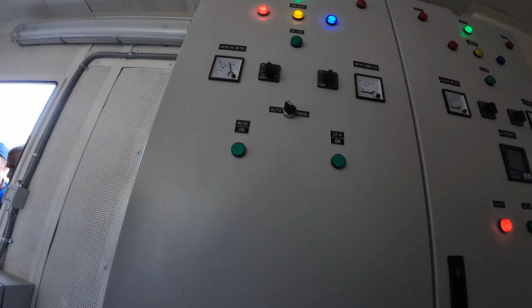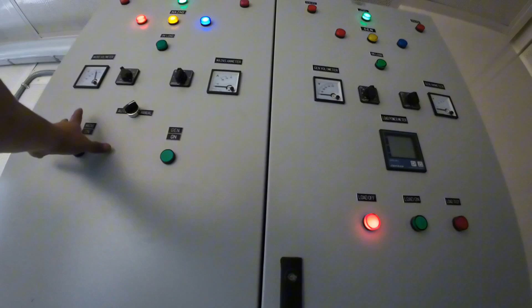Okay, so we will try to run this generator, so at least we have it available for our generator, so we can do manually for the genset close and for the mains close. For now it is closed from the mains because the mains is already live. So we'll try to close and start this generator so we can close manually for our control from the ATS.